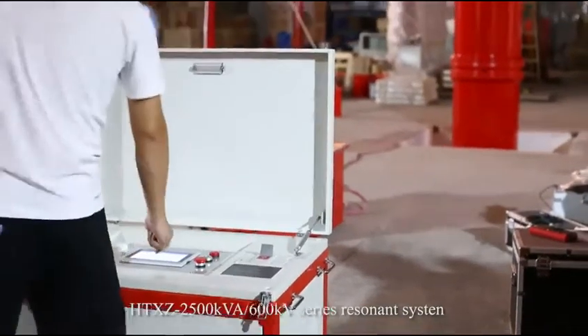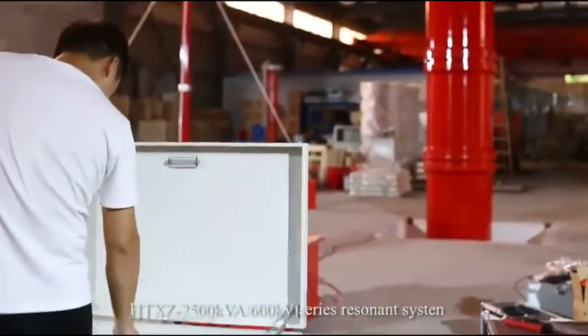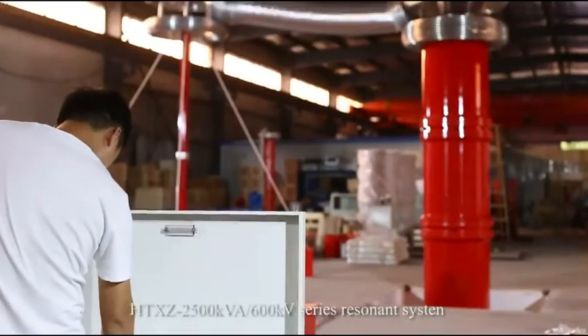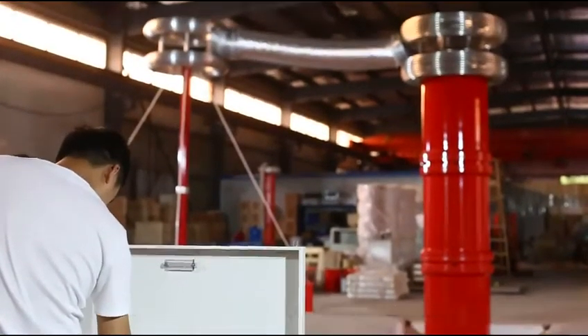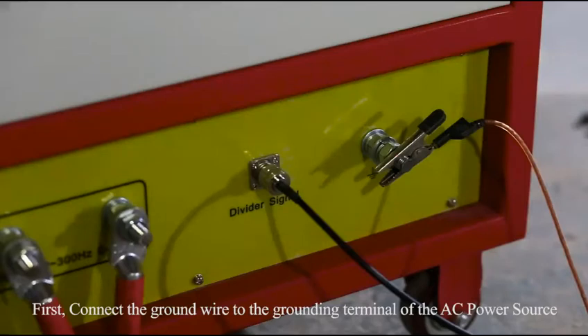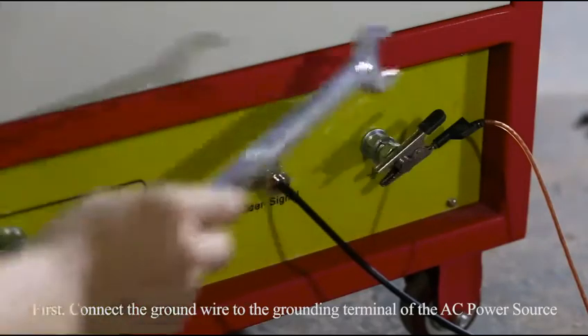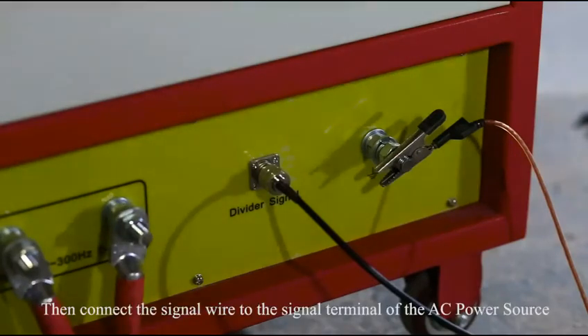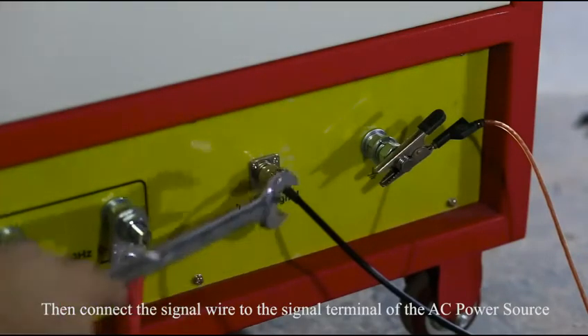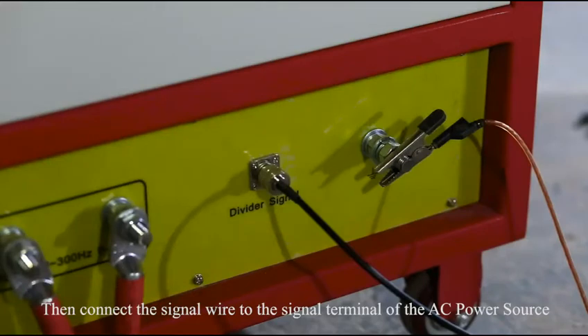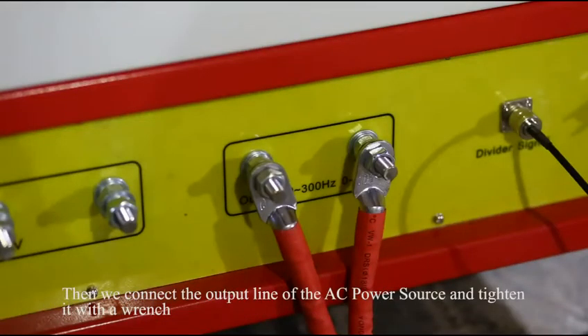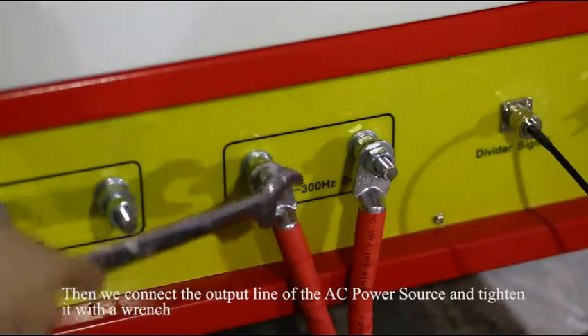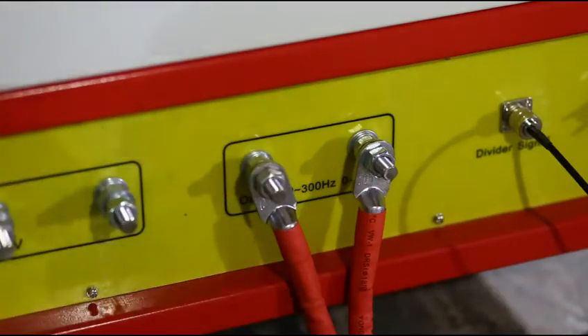HTXZ 2500 kVA 600 kV series resonant system. First, connect the ground wire to the grounding terminal of the AC power source. Then connect the signal wire to the signal terminal of the AC power source. Then we connect the output line of the AC power source and tighten it with a wrench.